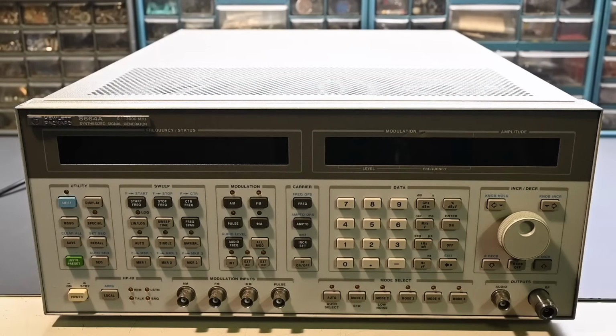If it does remember the settings and so forth, then I imagine that battery is holding up some charge, but again, it probably should be replaced given the age of the instrument. I also noticed that there's a lot of dust in the fan vent, so really the instrument needs to be taken apart for general servicing and cleaning. So I'll take you through that as I disassemble it. We'll have a look around inside the instrument.